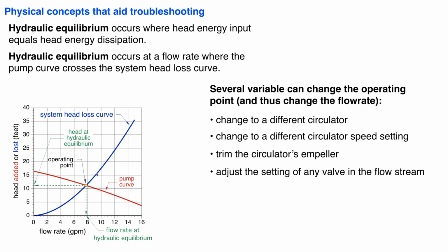Adjusting any valve in the flow path. If we have a balancing valve, even an isolation valve on a circulator, if we partially close that valve, we are changing that system curve. As we close the valve, this blue curve would get steeper and the operating point would move to the left to a lower flow rate.